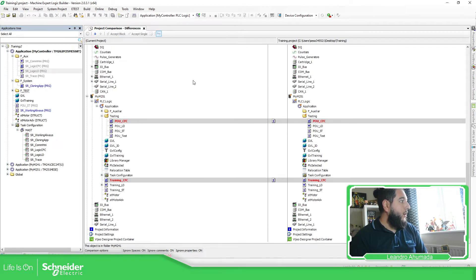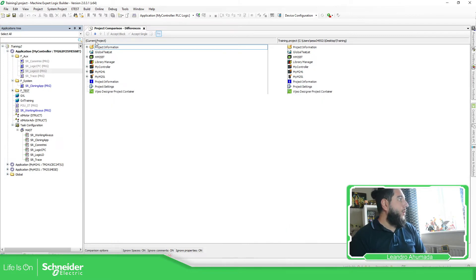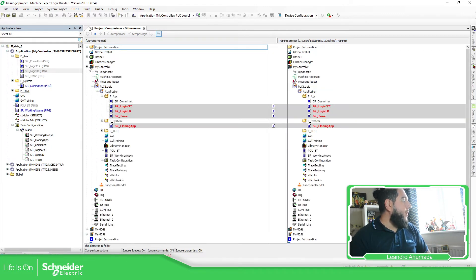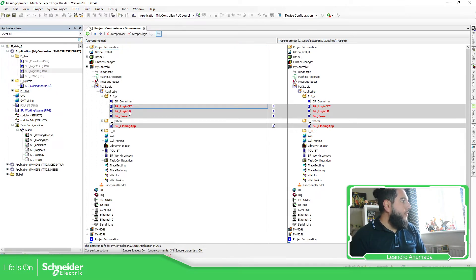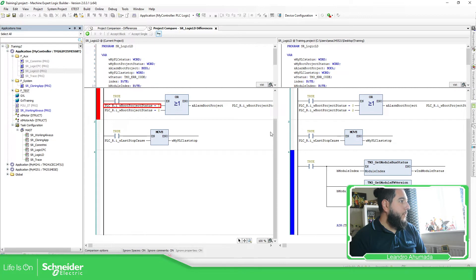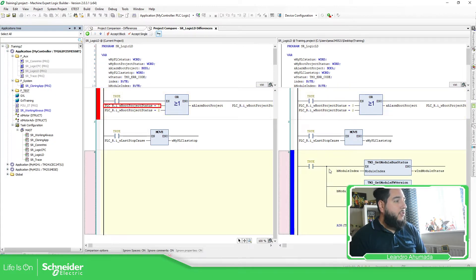So you can see over here that in this case I have three PLCs and one HMI, and it puts everything together. Let me minimize all this. So you can see here I have the current project, which is 'training two,' and on the other side is the 'training' project, the original one — you can see the path here. If I expand this part, you should be able to see in red the parts that have some differences. Let's try with the first one — the Logic. Here you should be able to see the indication of the differences. You can see the number five is different from the number zero, and this rung is new.